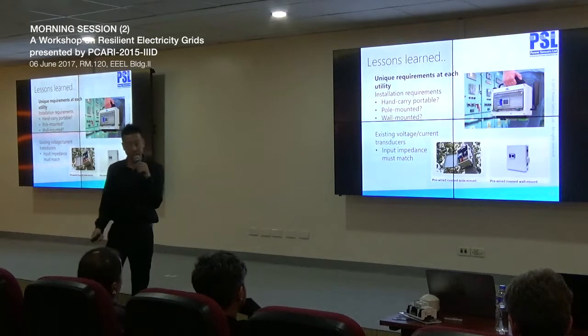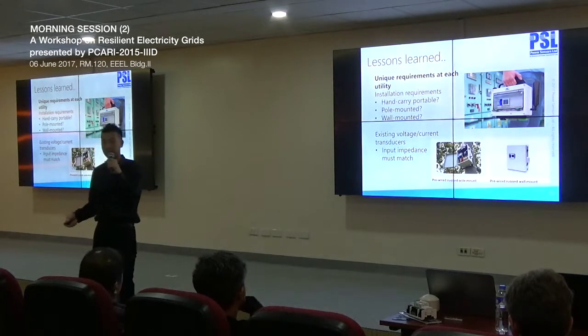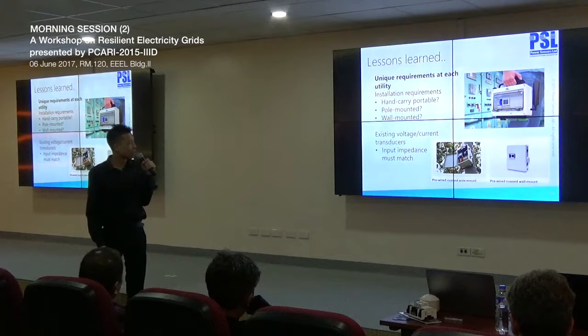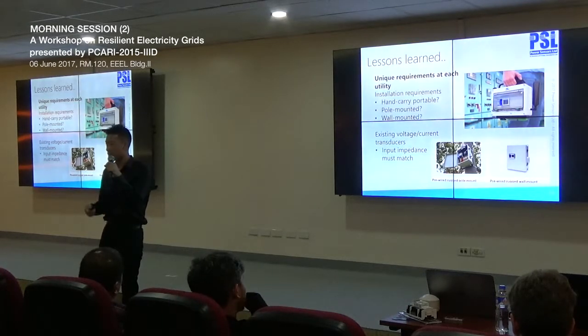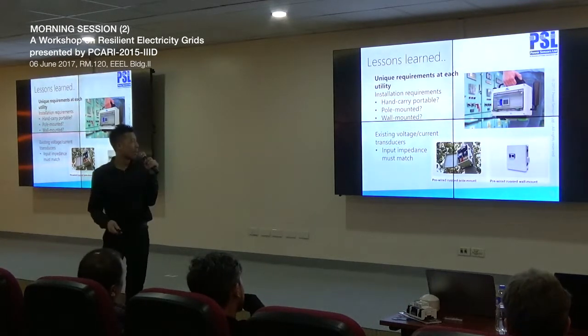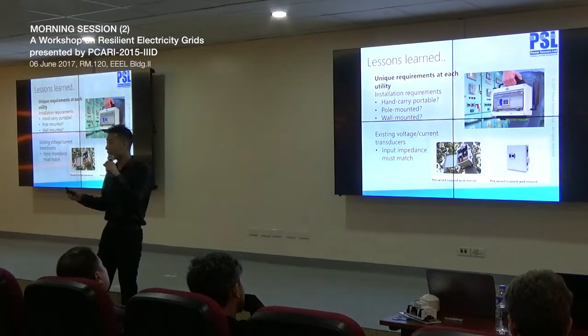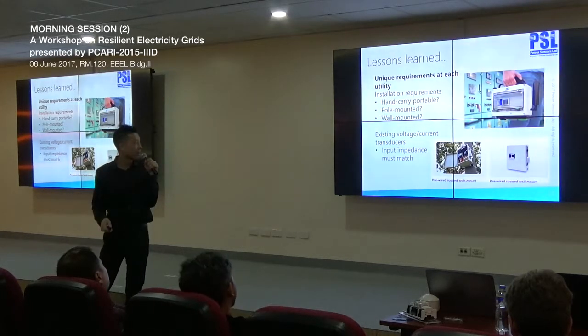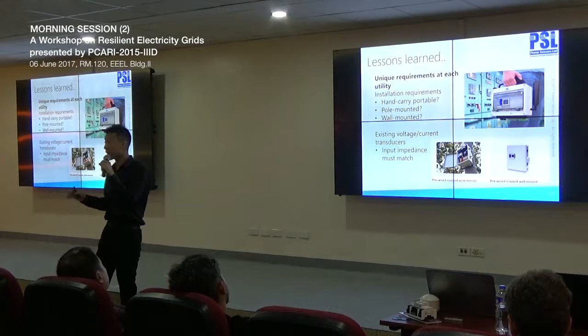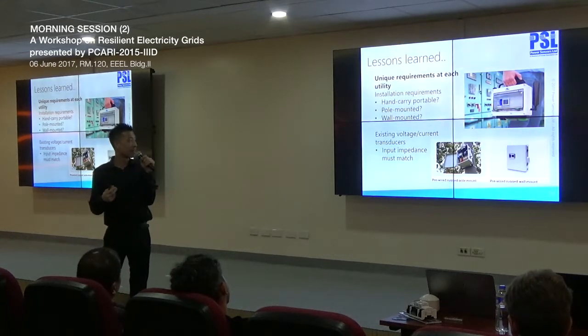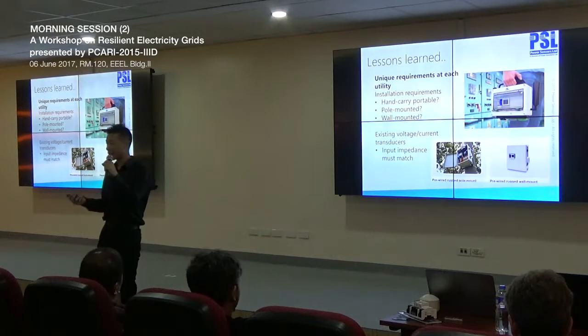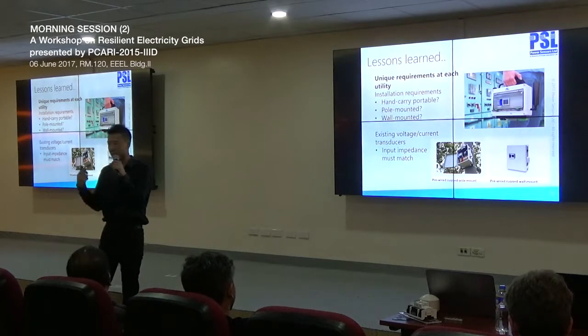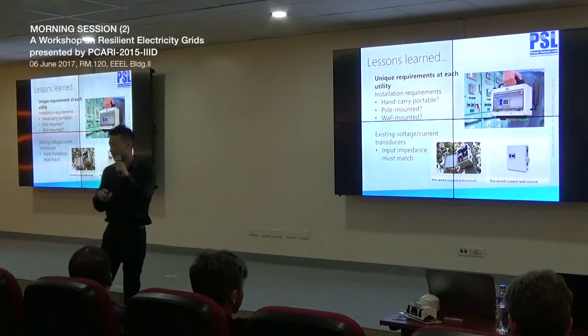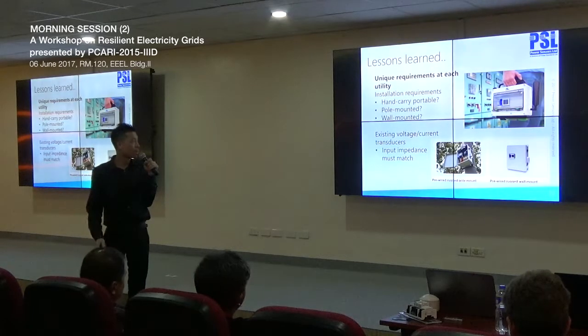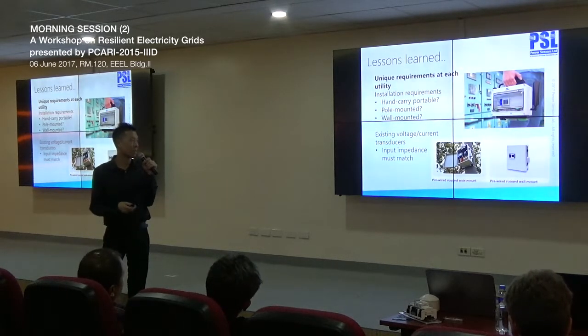A lot of utilities will already have voltage and current transducers. We need to make sure the input impedances match our PMU. The voltage inputs are about 5 mega ohm input impedance, and the current inputs are about 33K, which is by design to work with our current transformers. We observed some issues where our current channels were being clamped down to 0 because the input impedance did not match the transducer, but we were able to come up with a solution eventually through firmware.